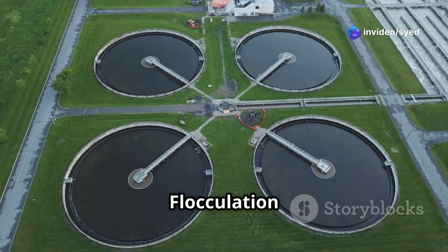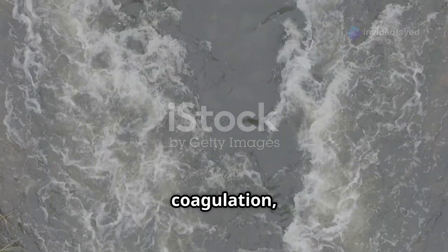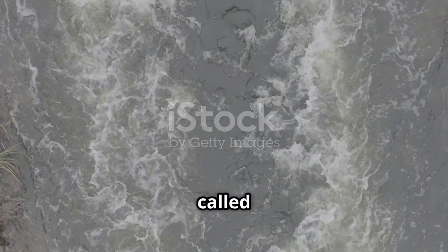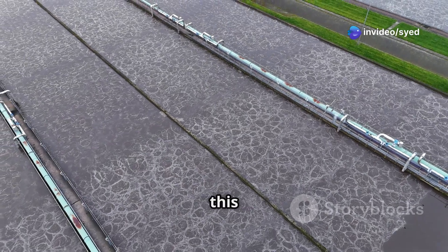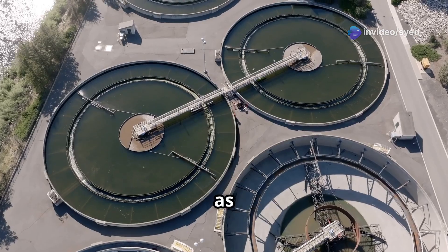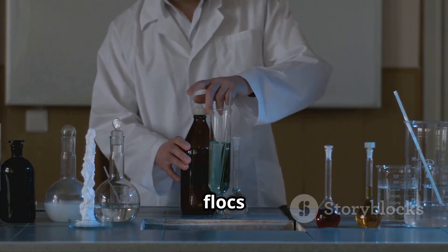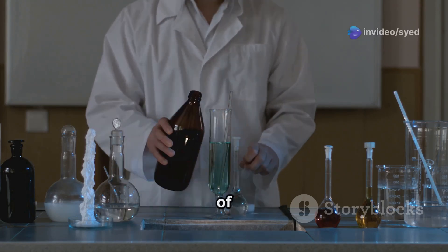Following coagulation, the destabilized pollutants begin to aggregate into larger particles called flocs. Gentle mixing or aeration is often employed during this stage to enhance floc formation. Larger flocs are advantageous as they are easier to remove from the wastewater. The size and strength of the flocs depend on factors such as pH, current density, and the type of pollutants present.